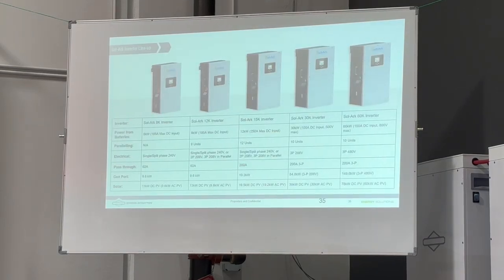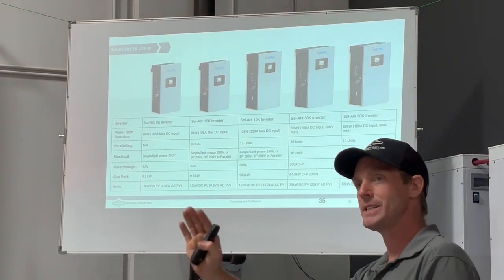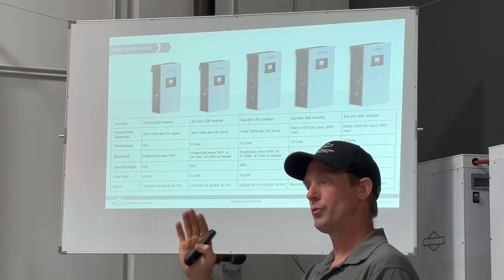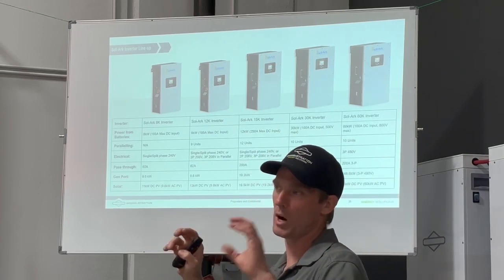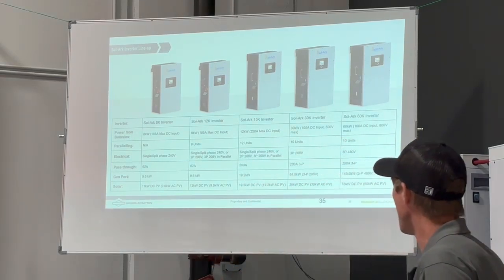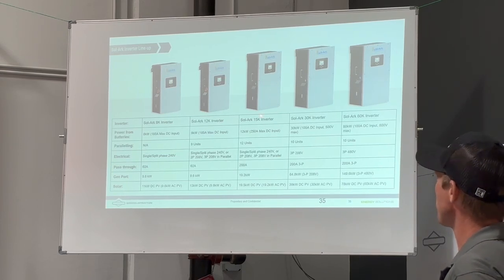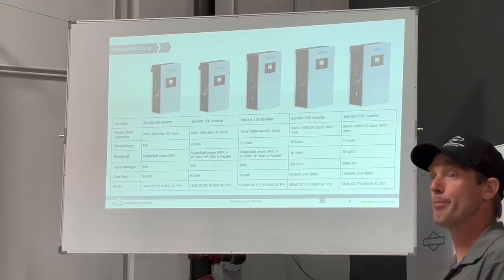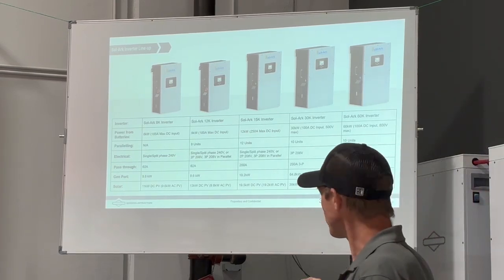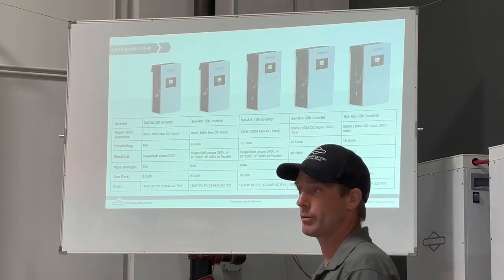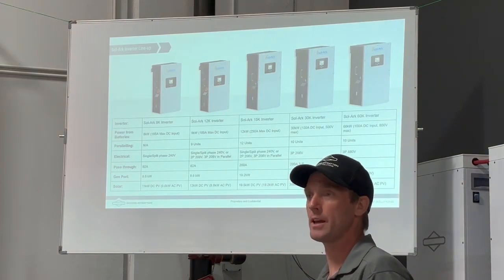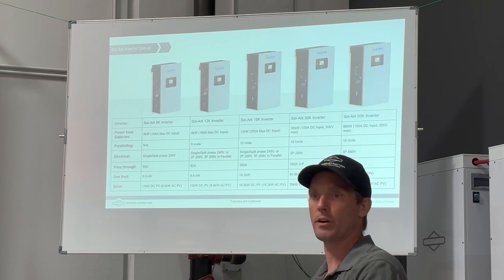Okay, so I was going to talk a little bit about the specs on the 15K right now. It's a 15K inverter, meaning it's capable of turning 15 kilowatts of DC electricity into 15 kilowatts of AC electricity, or approximately, there might be a little bit of losses. But it's only capable of turning 12 kilowatts from batteries into AC power. So if you want the full 15K, that's with solar on there as well.